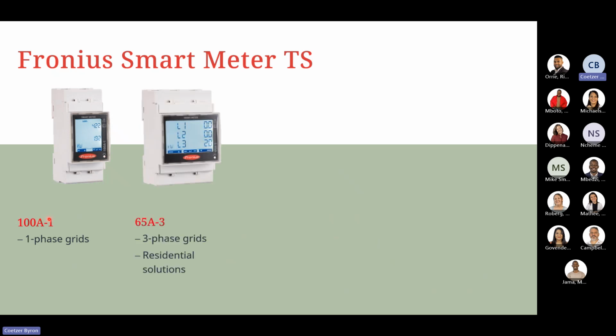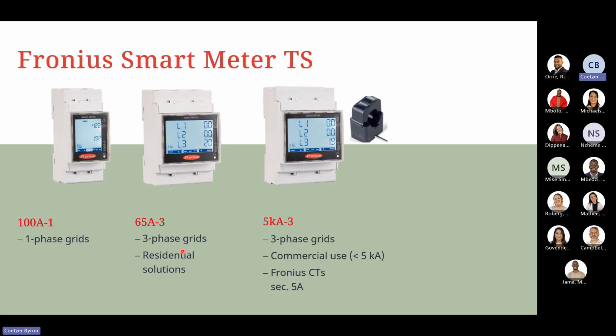For smaller commercial grids, we recommend using the 65A-3. Again, this is also a pass-through meter. For three-phase grids, small residential installations, and then for the larger commercial side, we recommend the 5KA-3. This is a CT meter, again for three-phase grids. We always recommend using the Fronius CTs, but you can use third-party CTs as long as the quality of the CT is very high.